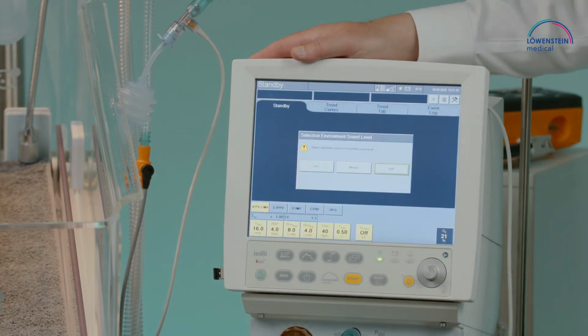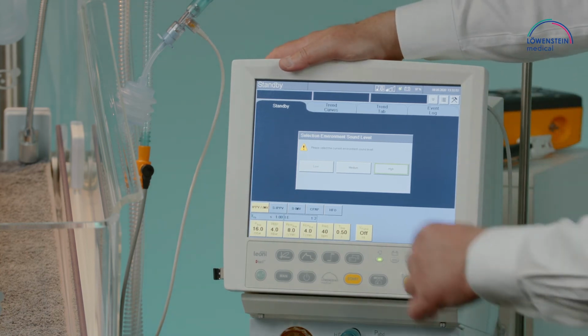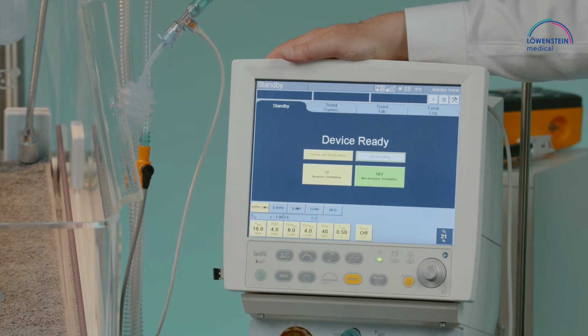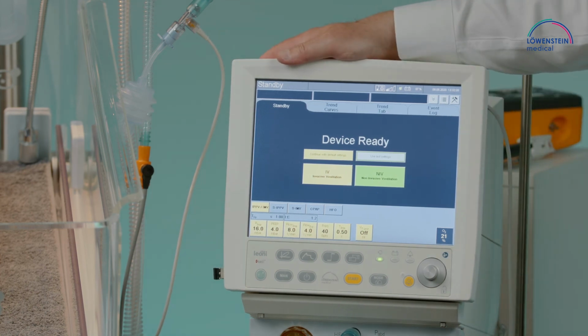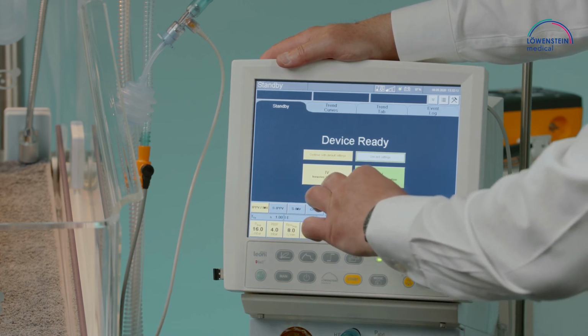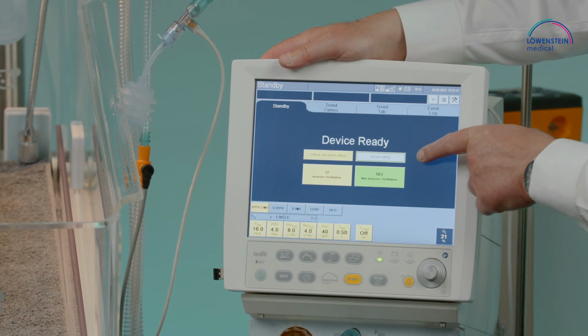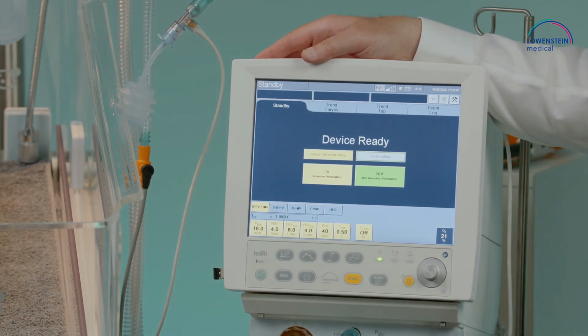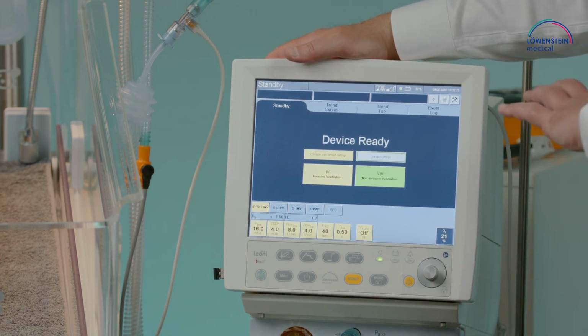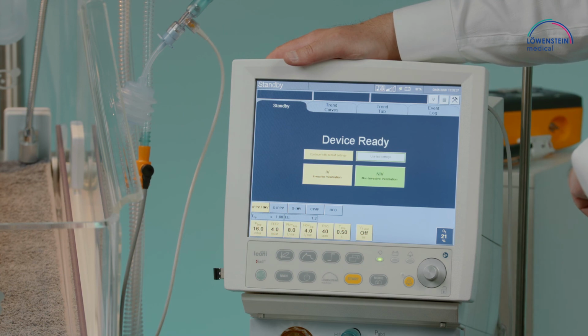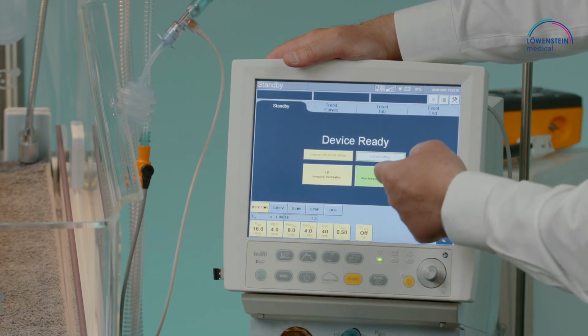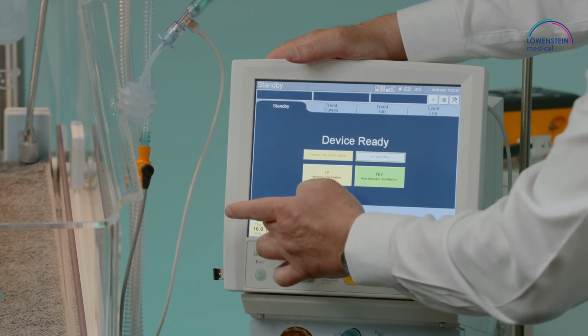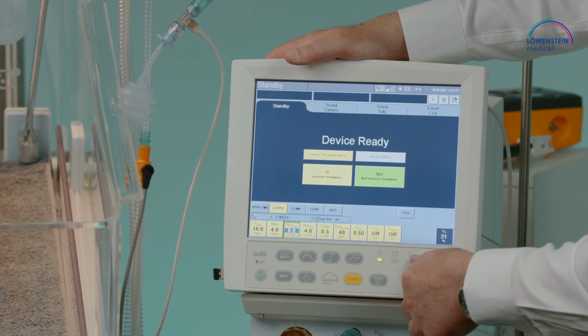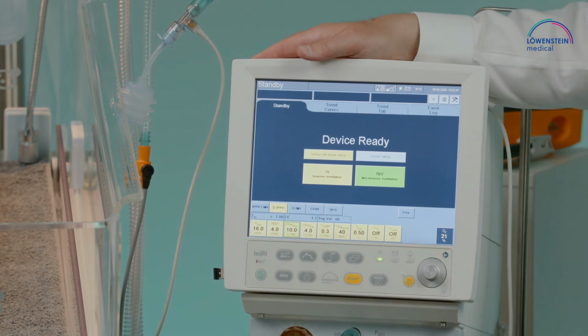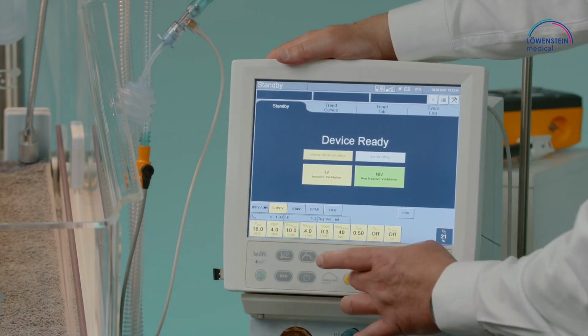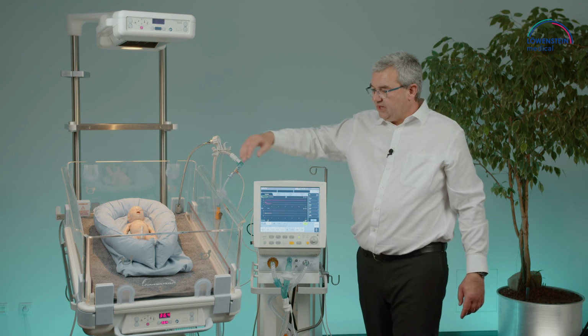Then we have the selection of ventilation. We can now decide on the acoustic alarm management. Is it low level with the alarm noise or high level? Then we have the opportunity to continue with the default settings or to use the last settings, from the last patient who has been ventilated. The information is in memory on the system and can be used. Then we have the selection of invasive ventilation or non-invasive ventilation, and the selection of the ventilation mode. We also have the opportunity to directly adjust parameters before we start. Now we can start the ventilator and connect it to the patient.